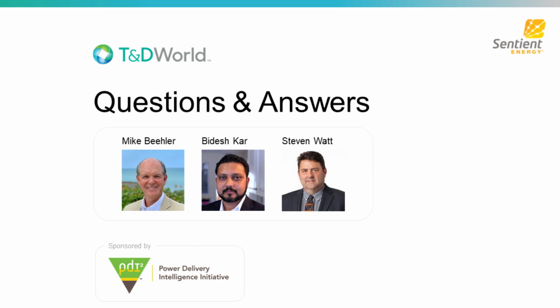Yes and no, so both. Let me answer the feeder example first. With UM3 Plus, if it's being installed in a dead front cabinet, you do not need to take an outage, you do a gloved install, there's no exposed energized part. If you're installing in a live front, yes, you'd take a cabinet-level outage. But for the UM3, if it's dead front, you can do a hot install.